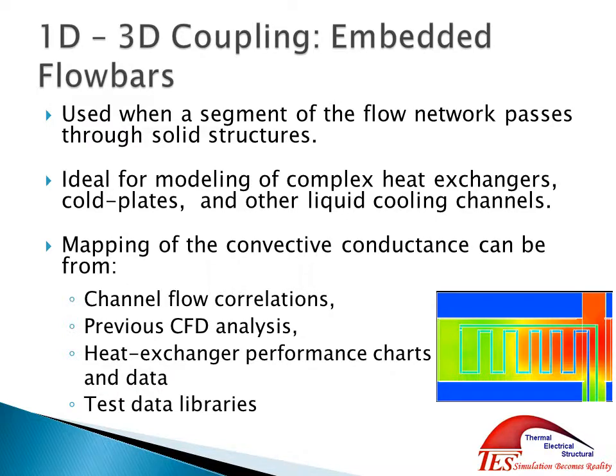Now we're going to talk in a little more depth about the actual embedding of 1D flow bars into the 3D. As you can see in this image, we have represented flow bars going through a cold plate in a full 3D model. The flow is handled completely on the 1D side, but it's picking up temperature through the 3D model, specified through either some kind of correlation, an H value from previous CFD analysis, or however you obtain that information. As the fluid comes in, it picks up temperature, adjusting how much heat it's pulling out of the 3D model. This is ideal for modeling any kind of liquid cooling channels, cold plates, or even complex heat exchangers in a 3D system.